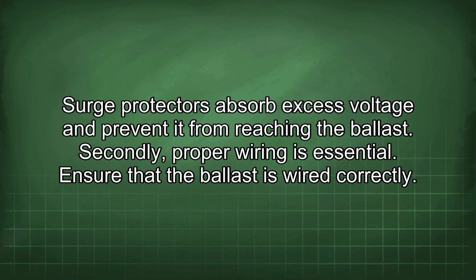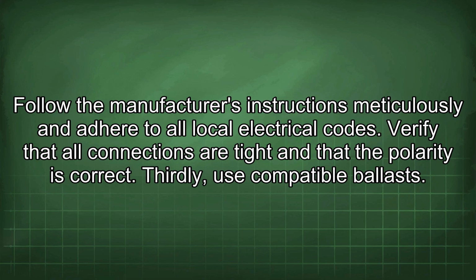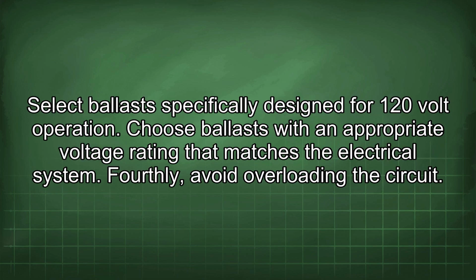Secondly, proper wiring is essential. Ensure that the ballast is wired correctly. Follow the manufacturer's instructions meticulously and adhere to all local electrical codes. Verify that all connections are tight and that the polarity is correct. Thirdly, use compatible ballasts. Select ballasts specifically designed for 120-volt operation. Choose ballasts with an appropriate voltage rating that matches the electrical system.